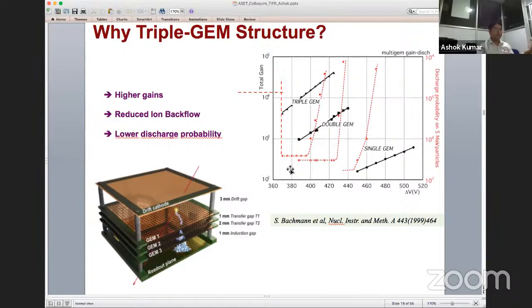So if you amplify it considerably, the thresholds for the front end to pick up can be considerably finer. It depends on how much threshold your ASIC can handle. So it is important that your natural amplification inside the detector is very, very large, and it also helps in the signal to noise ratio.